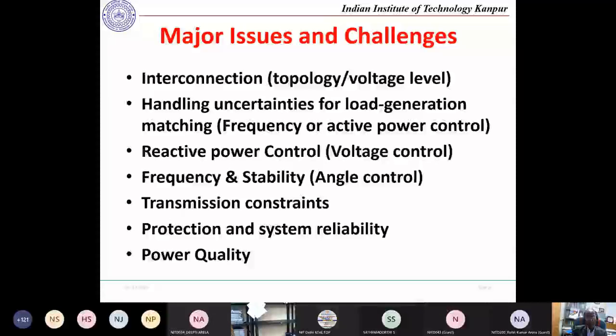Another concern is protection and reliability, because many of these devices involve DC current that needs protection — similar to what we normally do in HVDC. We work through the controller of the converter itself, since we don't have circuit breakers for this, though now ABB and others are making commercial DC circuit breakers. Normally the philosophy of HVDC lines is based on voltage control, controlling even through the converter station's controller.